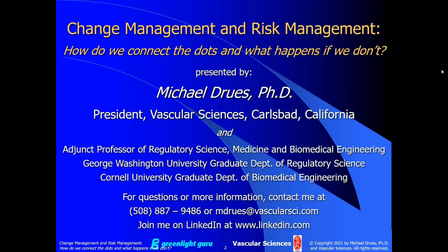So we have a device that's at design freeze. It's not on the market yet because we're still presumably in the clinical trial, but we make a change to it. Well, one of the first questions I would ask Tori and Andreas is, how do you define design freeze? Because if you're still making changes after you've gotten design freeze, then what the heck does the design freeze mean? That said, let's not talk about the semantics of what design freeze means. Here's the concern that I have. Does that change potentially impact the results of that clinical trial?